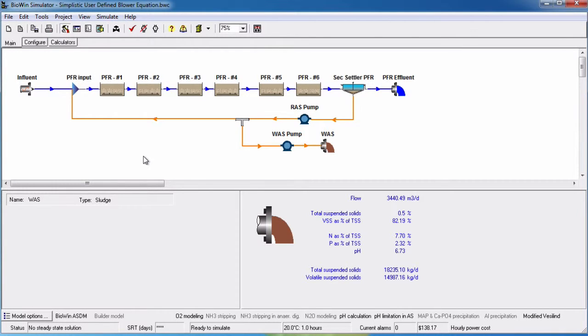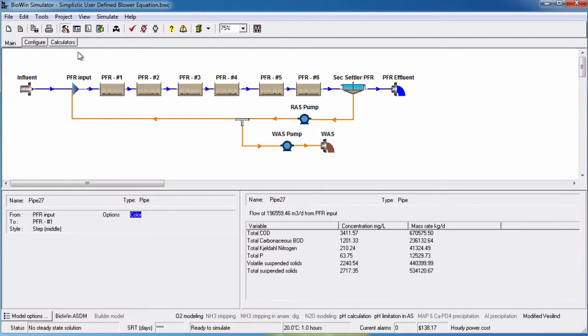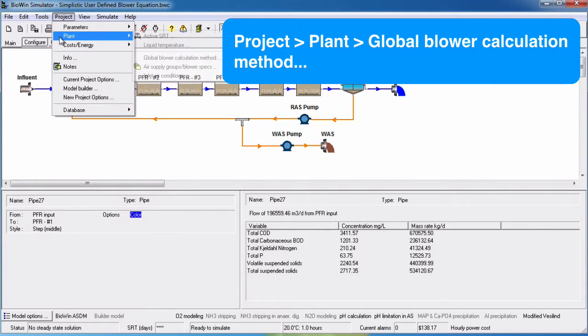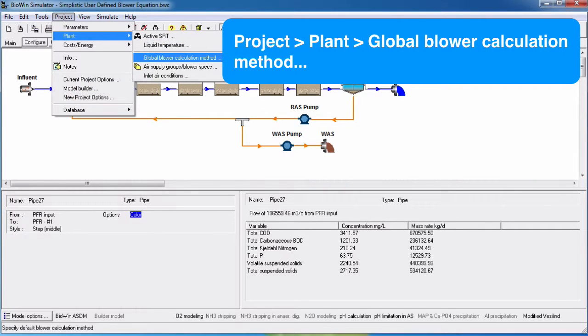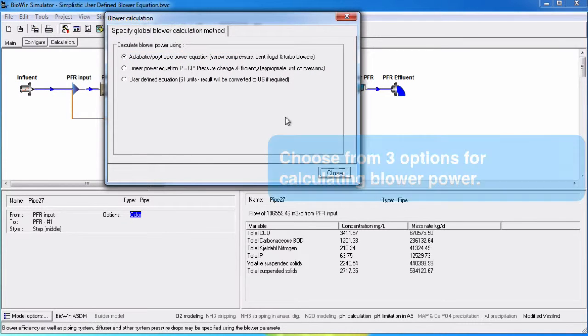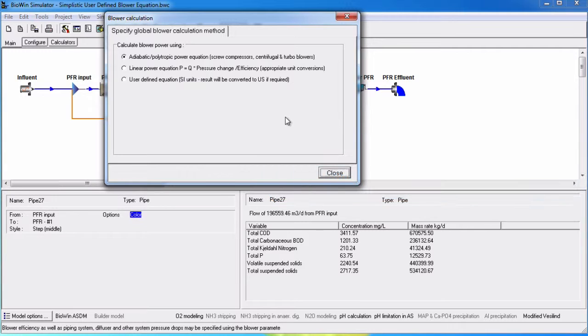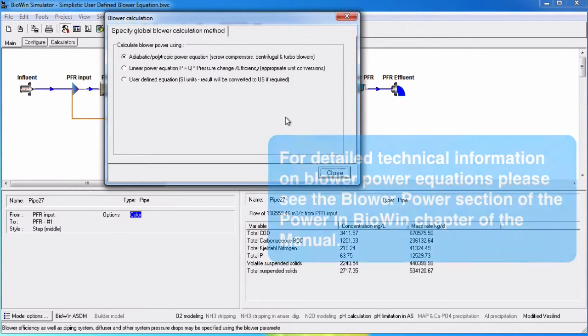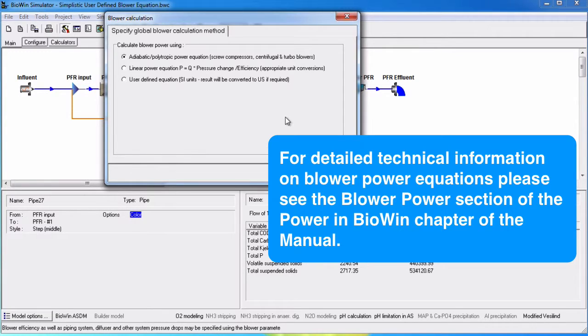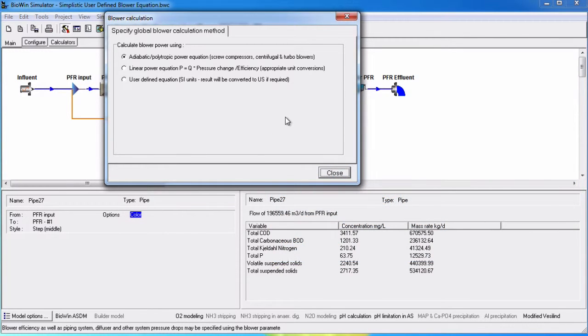Before we define an air supply group, we can specify a global blower power calculation method for a project under Project, Plant, Global Blower Calculation Method. Here we can choose from three options for calculating blower power: the adiabatic polytropic power equation, a linear power equation, or a user-defined equation. Detailed technical information about the blower power equations is provided in the blower power section of the Power in BioWin chapter of the manual.